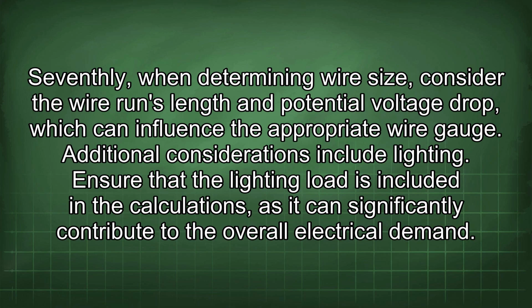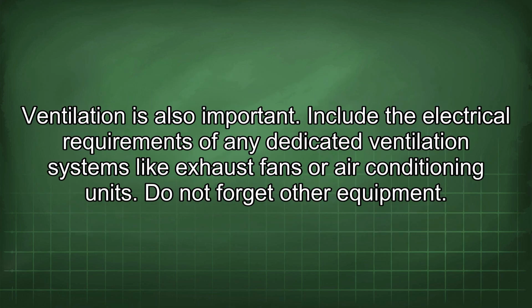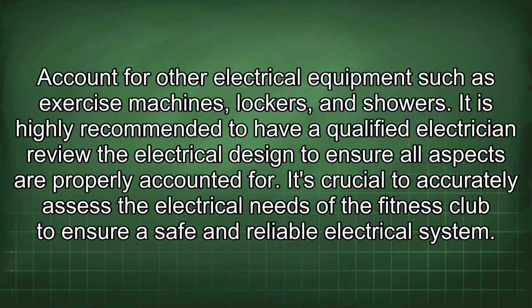Ensure that the lighting load is included in the calculations, as it can significantly contribute to the overall electrical demand. Ventilation is also important. Include the electrical requirements of any dedicated ventilation systems like exhaust fans or air conditioning units. Do not forget other equipment. Account for other electrical equipment such as exercise machines, lockers, and showers.